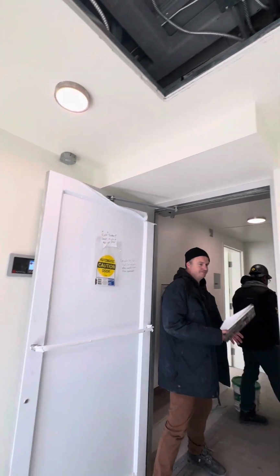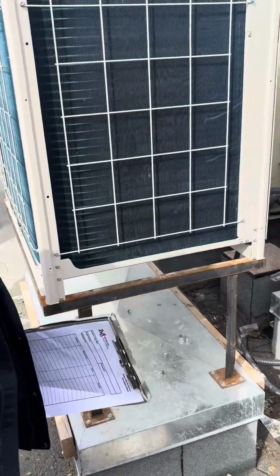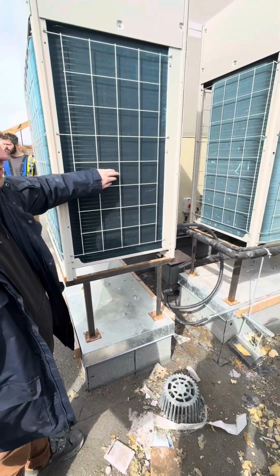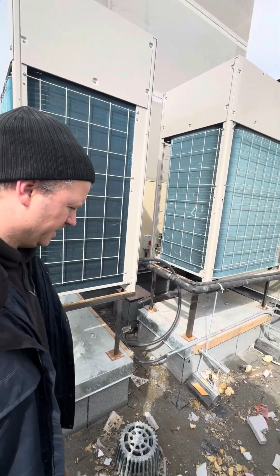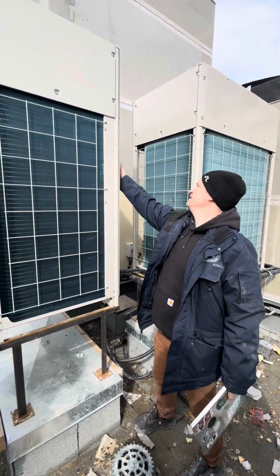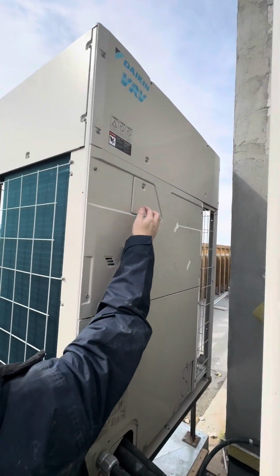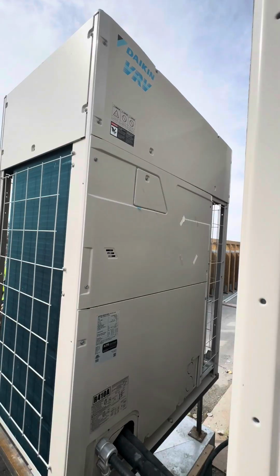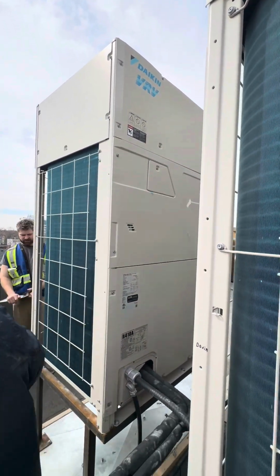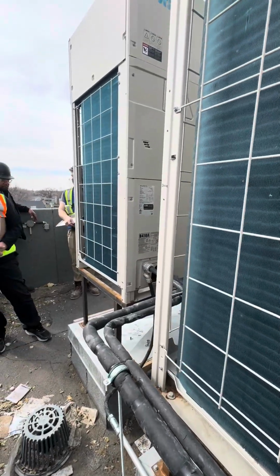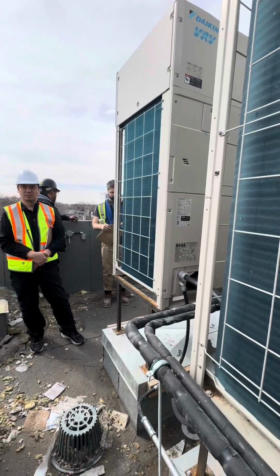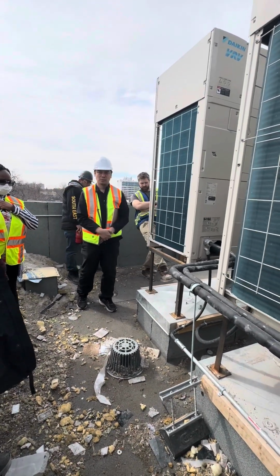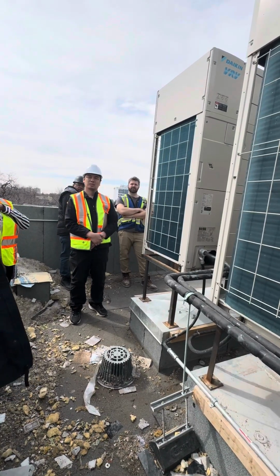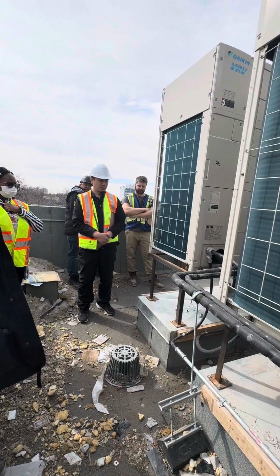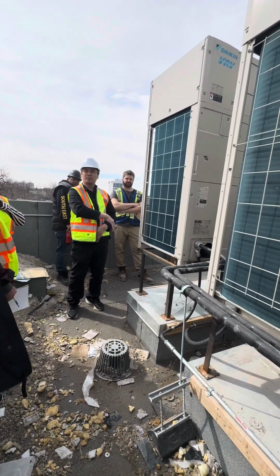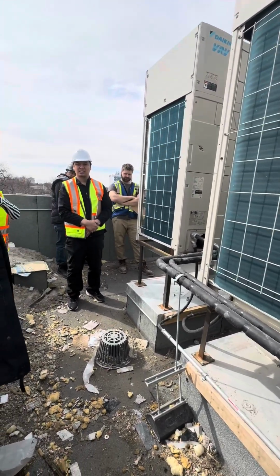Anything special with this, other than maintenance-wise? Once a year likely you're going to take the pressure washer and wash the condenser coils. On the inside there's a board that will give you any codes or anything like that. There's just one screw for this panel, and then there's a little peephole to look in, but everything you get from here essentially will be on that panel. You shouldn't ever have to come up here other than to do maintenance, just know where they are so you can send your contractor to look at them. If we're going to wash the coils, yes, we have to turn off the system.